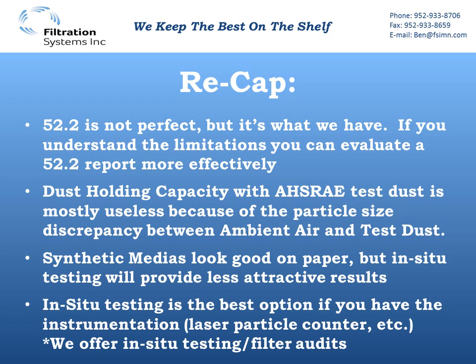To recap: 52.2 isn't perfect, but it's what we have. If you understand the limitations, you can evaluate a 52.2 report more effectively. Dust holding capacity with ASHRAE dust is mostly useless because of the size discrepancy between ambient air dust and the test dust. Synthetic medias will look good on paper, but when you do an in-situ test, they'll be a lot less attractive. In-situ testing is the best option if you have the instrumentation — mainly a laser particle counter, as the other measurements can usually be done with even basic control systems.